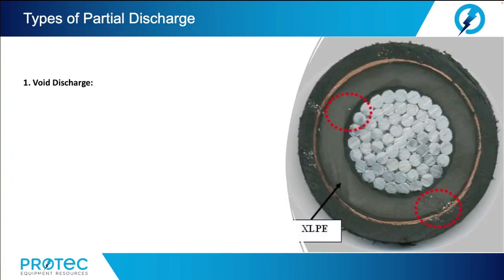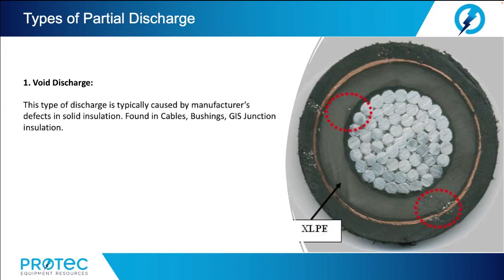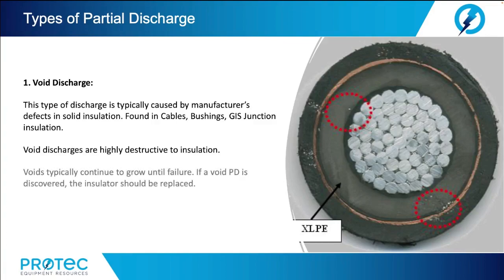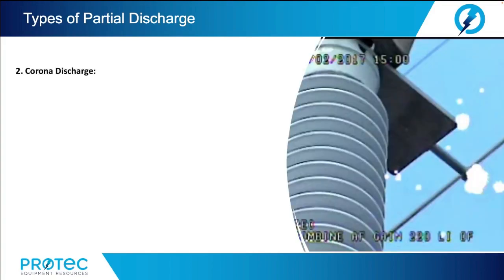So let's take a look at some of the types of partial discharge. First, the void discharge. This type of discharge is typically found in manufacturers' defects in solid insulation. It can be found in cables, bushings, GIS junction insulation. Void discharges are highly destructive to insulation. And voids typically continue to grow until failure. If a partial discharge is discovered, the insulator should be replaced.